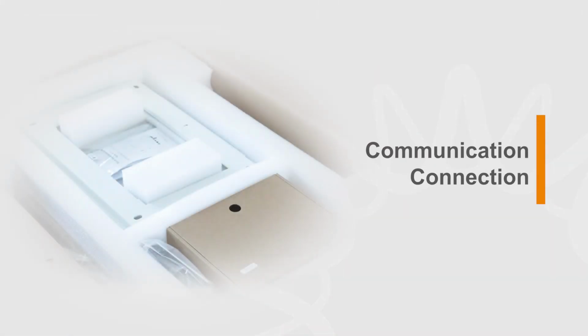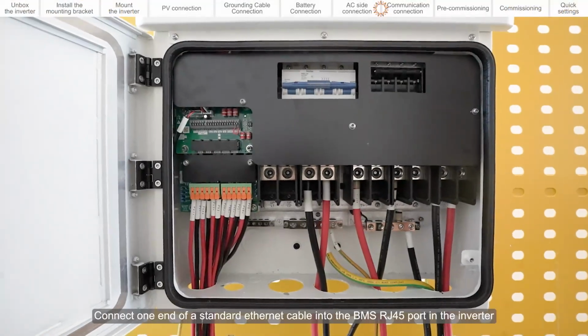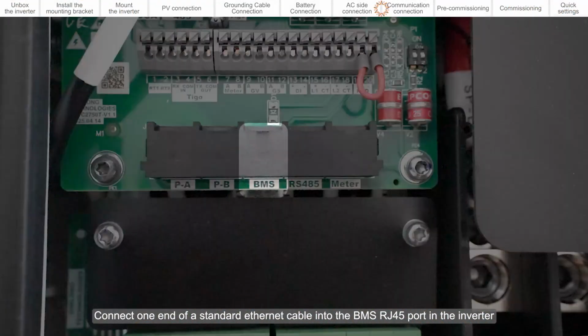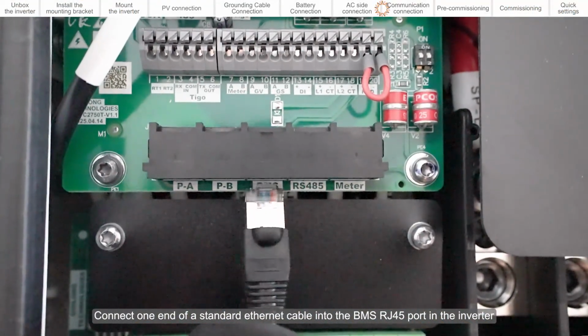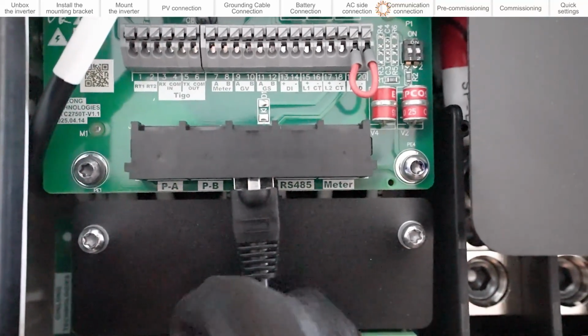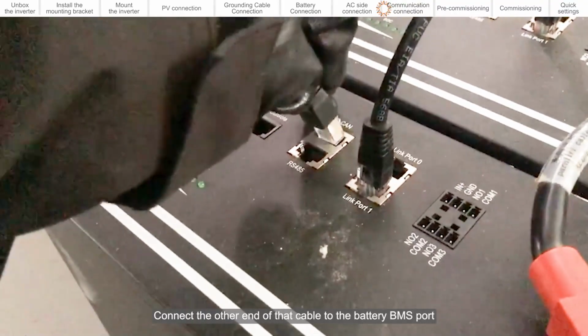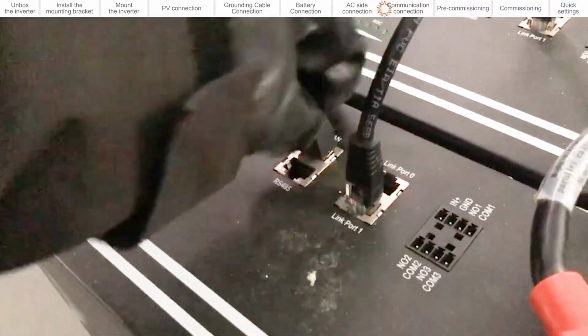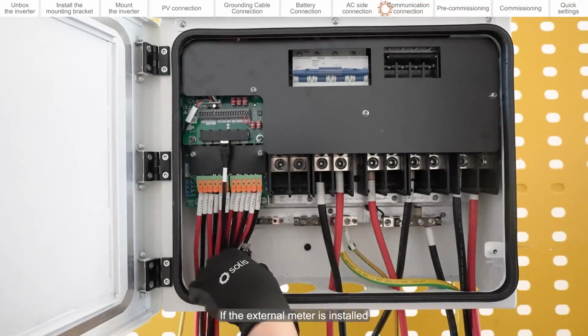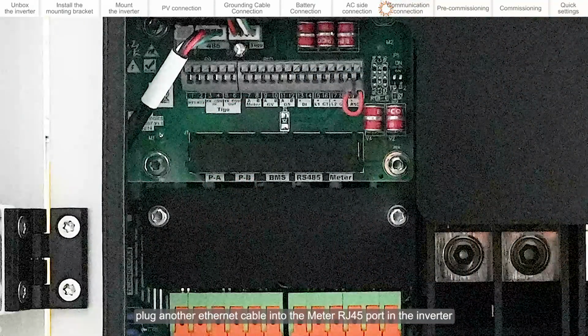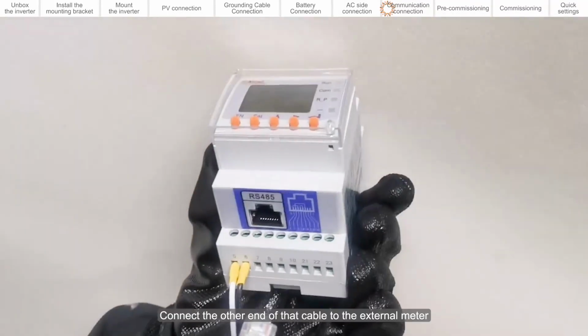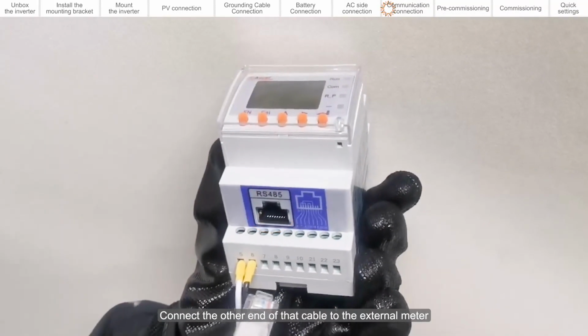Communication connection. Connect one end of a standard Ethernet cable into the BMS RJ45 port in the inverter. Connect the other end of that cable to the battery BMS port. If the external meter is installed, plug another Ethernet cable into the meter RJ45 port in the inverter. Connect the other end of that cable to the external meter.